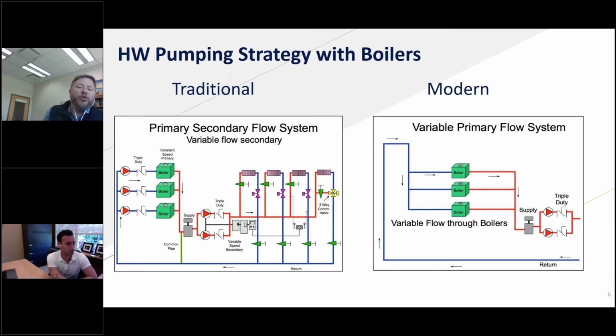That is made even more important as we look at modular boilers. Instead of using 1 or 2 large boilers sized for the full capacity, we start breaking that into smaller chunks. By doing that, we're not only creating a system that can respond across a wider range of operation from a capacity standpoint, it can also respond to a much wider range of flow. The design flow down to its minimum becomes near zero, because we've got multiple modular condensing boilers that have the ability to turn down to, call it, 10 or 20% of their design flow. If I now have 6 or 8 or 10 of those, that's how we're approaching full turn down, almost to zero.